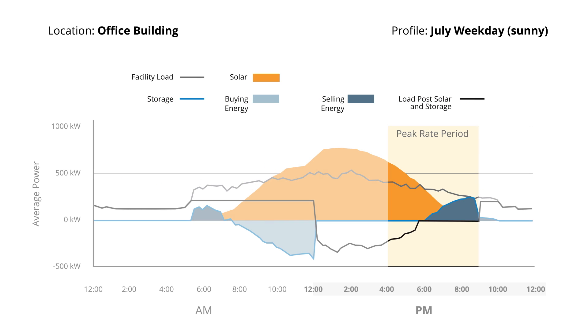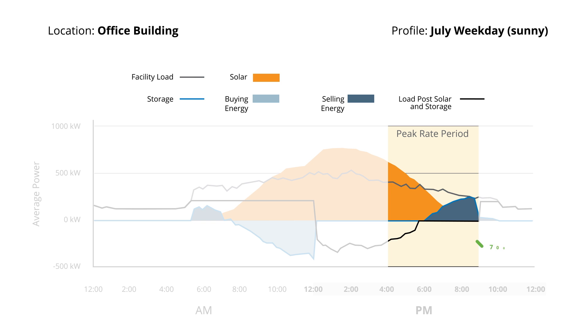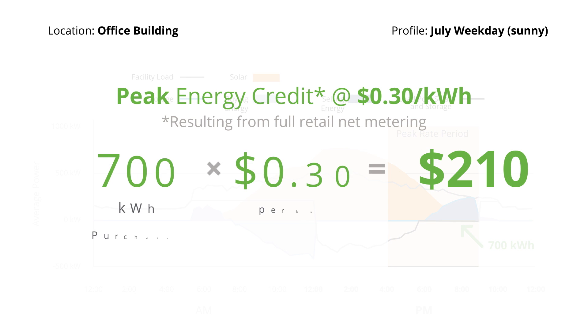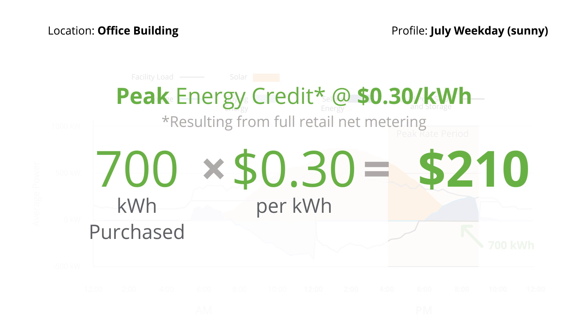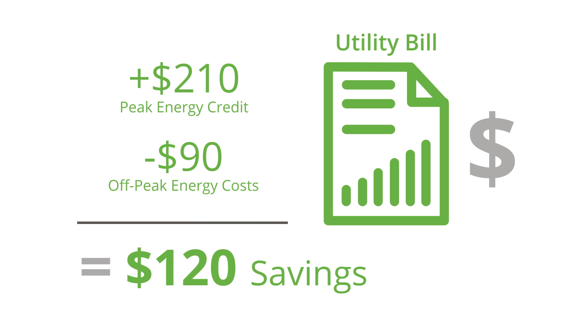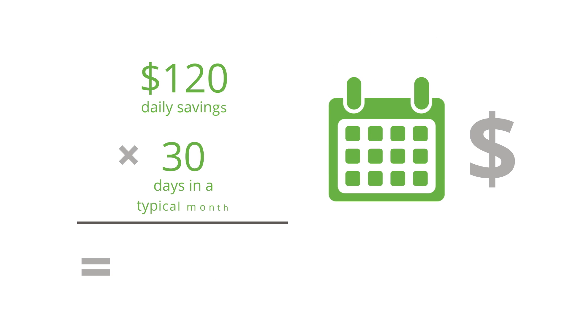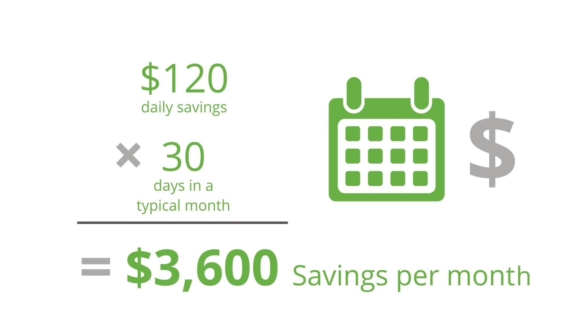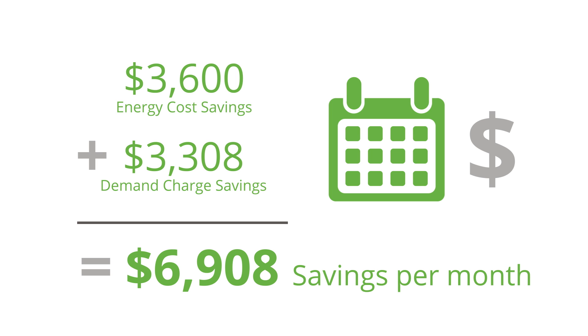There's a different story to tell during the more expensive peak rate period. Sunvault DX storage doesn't charge or buy any energy during this time of use. Instead, it only discharges or sells — 700 kilowatt hours to be exact — which calculates to $210, or 700 times the peak period rate of 30 cents per kilowatt hour. By subtracting what the customer pays for energy during off-peak hours from the energy credit they receive from discharging during peak hours, the total savings is $120 on this typical summer day. Multiply that by 30 and Sunvault DX storage would save this customer $3,600 during a typical summer month — additional energy savings on top of solar alone, and not even accounting for any demand charge savings.